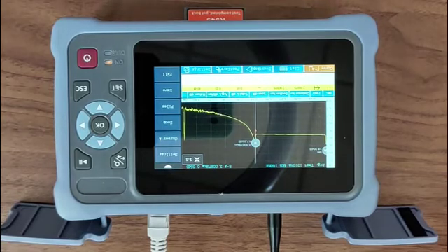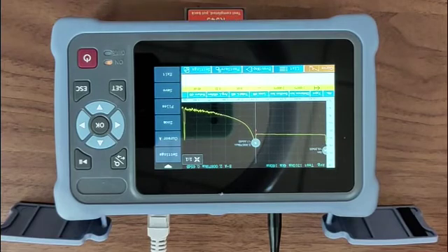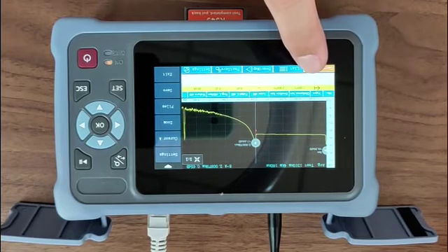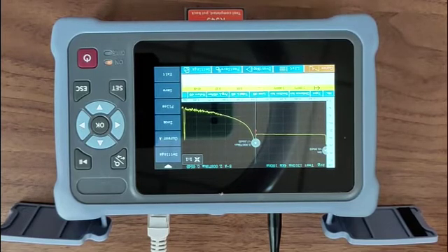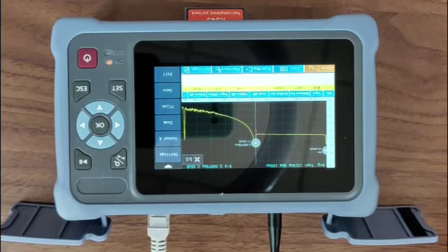When the test is completed, a list of events is generated in the event list. Type refers to the type of current event, including rising event, falling event, optical fiber starting point and ending point, and so on. Distance is the location of the current event. Section refers to the distance between two event points.